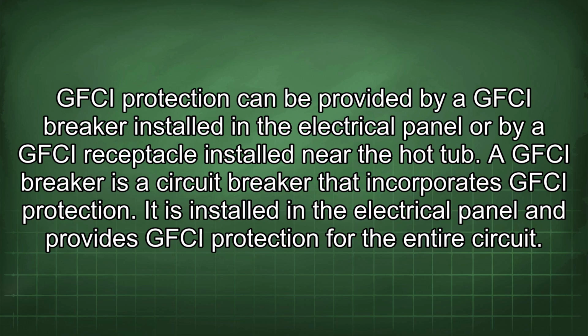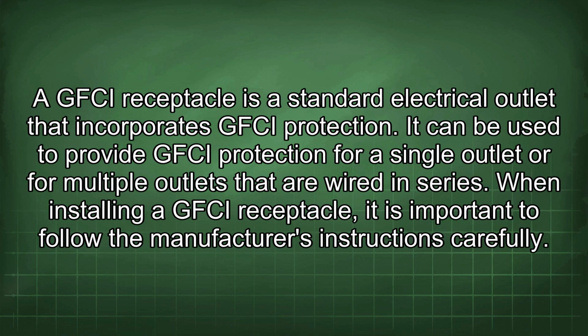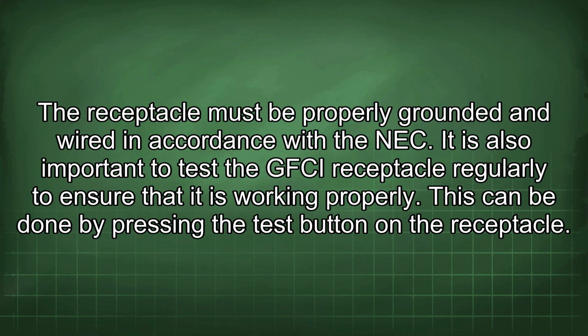It is installed in the electrical panel and provides GFCI protection for the entire circuit. A GFCI receptacle is a standard electrical outlet that incorporates GFCI protection. It can be used to provide GFCI protection for a single outlet or for multiple outlets that are wired in series. When installing a GFCI receptacle, it is important to follow the manufacturer's instructions carefully. The receptacle must be properly grounded and wired in accordance with the NEC.